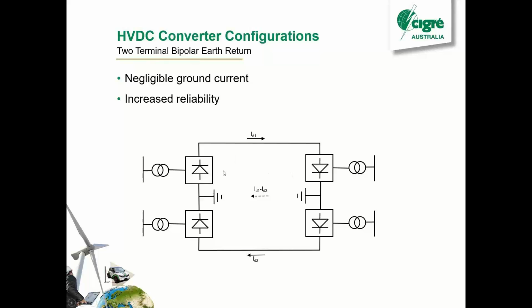So if you're balanced, if each pole is sending the same amount of current, then you can see we'll have no current in the earth return path. And that's the way we operate here in New Zealand most of the time. The poles are balanced and we'll have no earth return current. But if one of the poles trips for whatever reason, the full current will then go into the earth, and we'll be able to maintain transfer with just one pole.